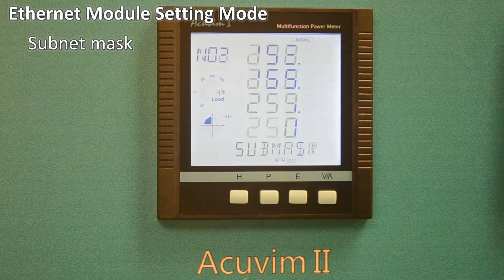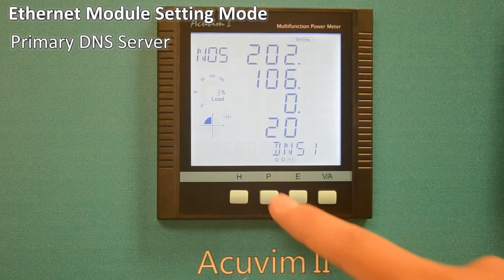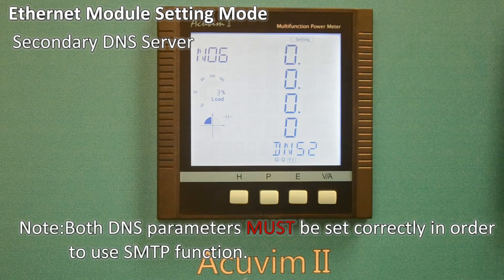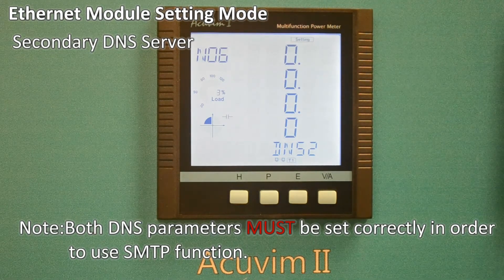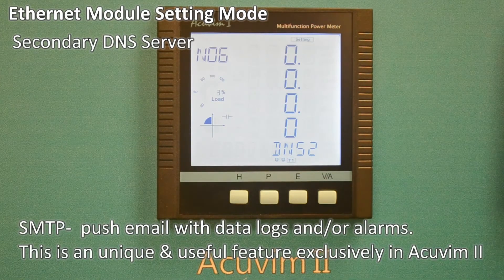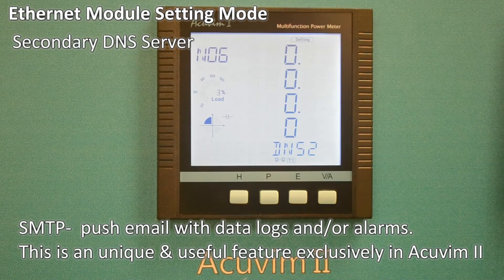The same method of setting can be applied to the subnet mask, gateway, DNS primary, and DNS secondary servers in subsequent screens. Please note: both DNS parameters must be set correctly in order to use the SMTP function. This ensures that functions such as push email with data logs and alarming features are working properly. The push email function is a unique and extremely useful feature of the Acuvim II series power meter.